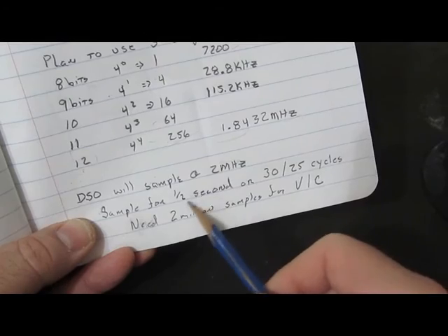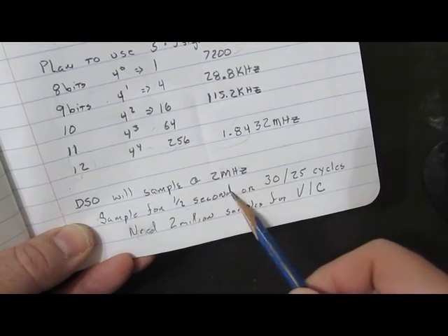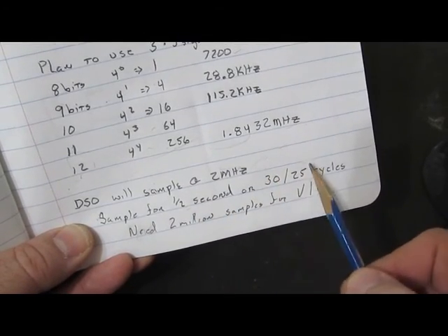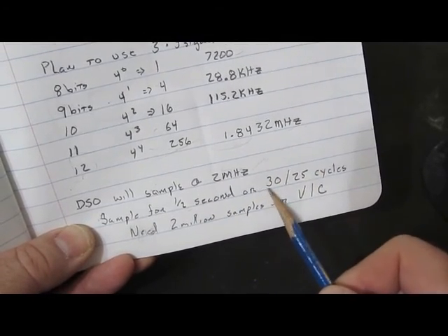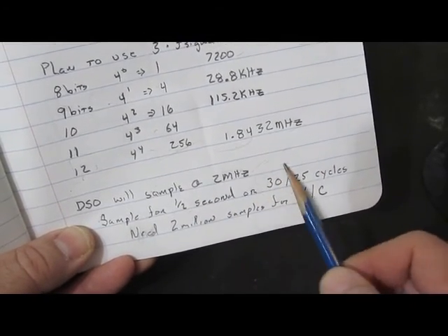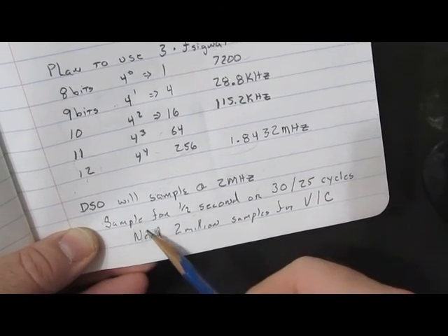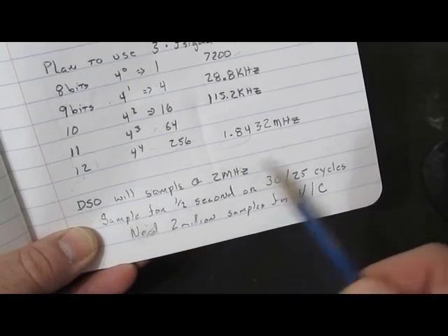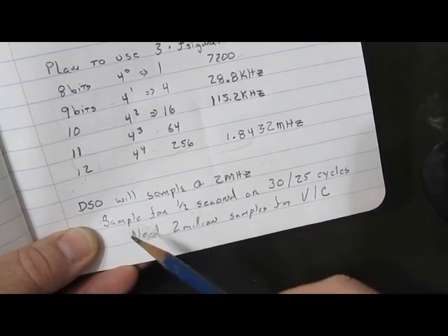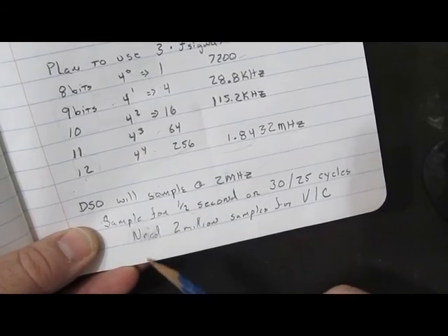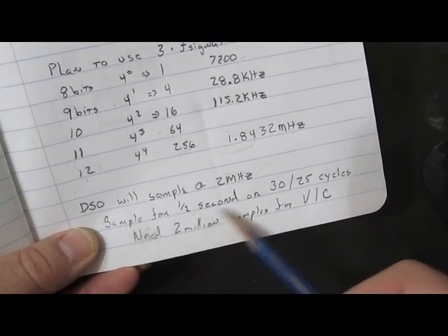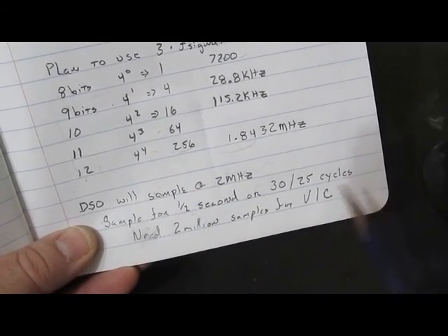If we capture the data for half a second, depending on if we're looking at 60 or 50 hertz, we're going to have either 30 or 25 cycles collected. If we look at how much data we're having to pull off the scope, for every half second, it's going to be two million points, or a million for the voltage and a million for the current.